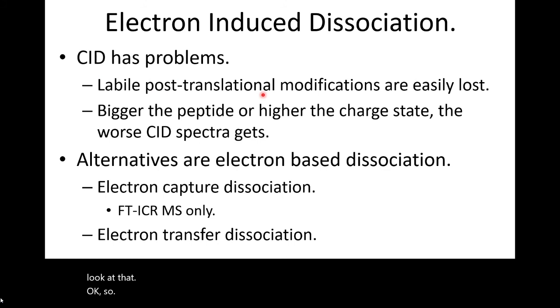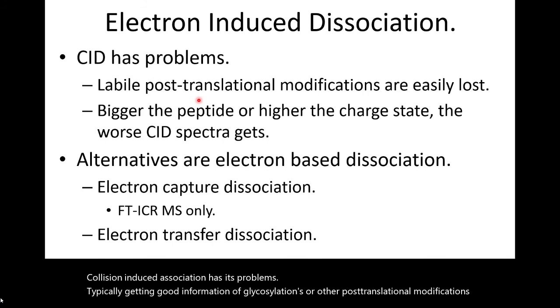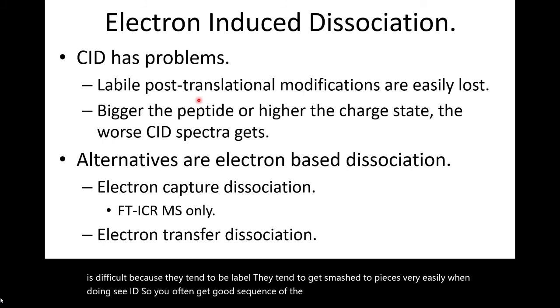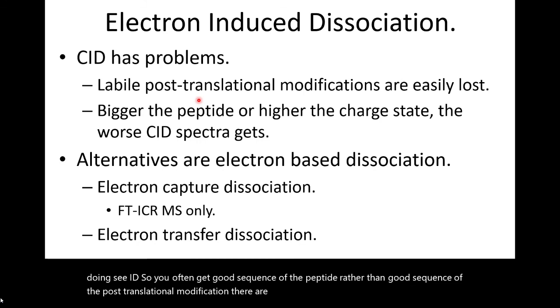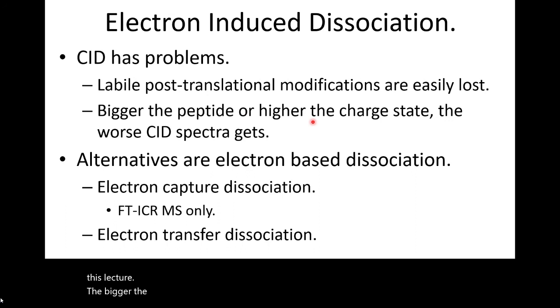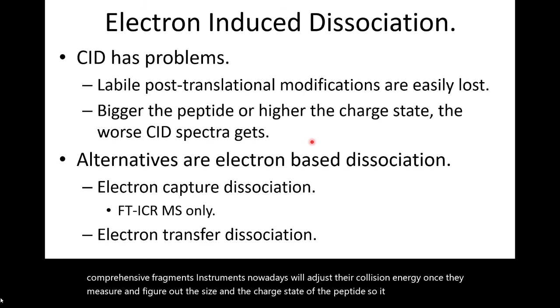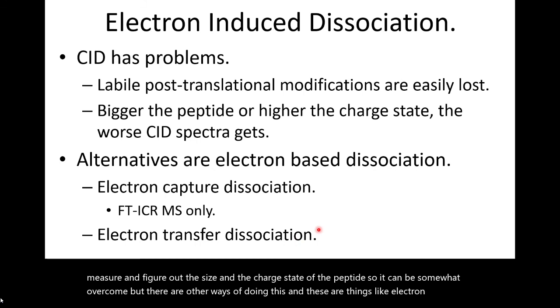Collision induced dissociation has its problems. Getting good information off glycosylations or other post-translational modifications is difficult because they tend to be labile — they get smashed to pieces easily with CID, giving good peptide sequence rather than good PTM sequence. The bigger the peptide or the higher the charge state, the more difficult it is to get comprehensive fragments. Modern instruments will adjust their collision energy once they measure the size and charge state of the peptide, but there are other approaches: electron capture dissociation and electron transfer dissociation.